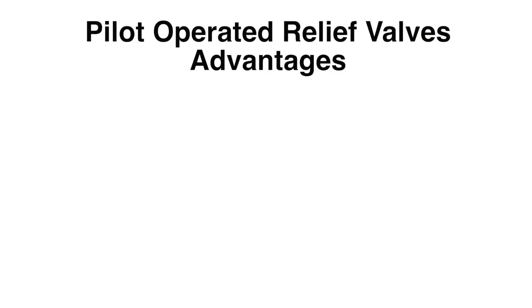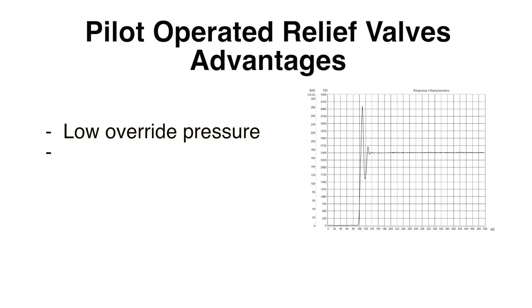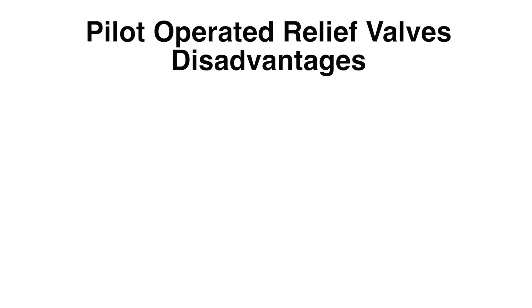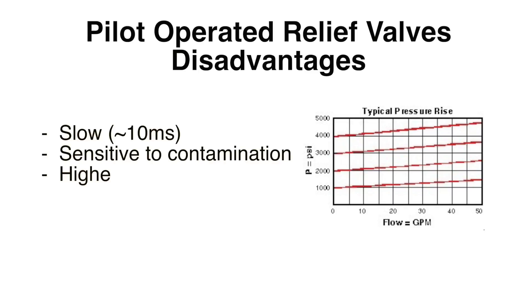Comparing pilot operated relief valves to direct acting valves, you'll notice some differences. Pilot operated valves have lower hysteresis, lower override pressure, and are generally adjustable under pressure. Relatively speaking, pilot operated valves are much slower than their direct acting cousins. They are also sensitive to contamination and have higher leakage rates.